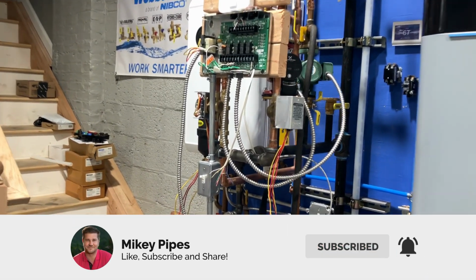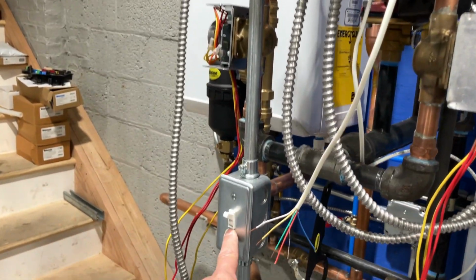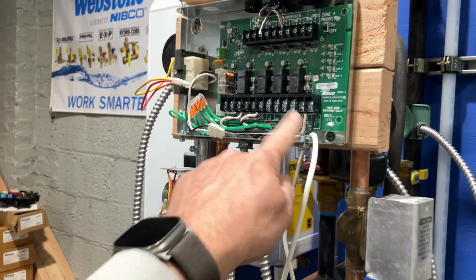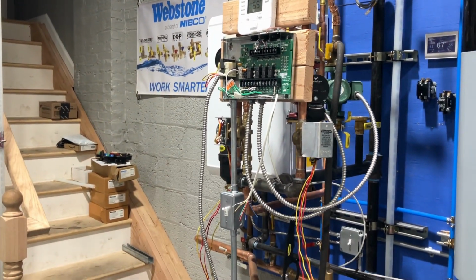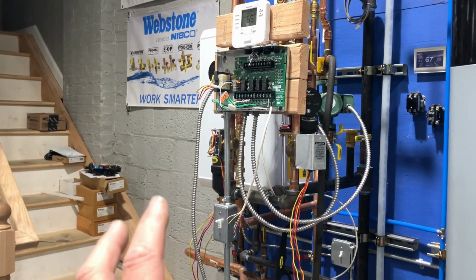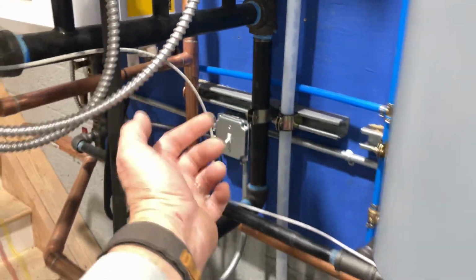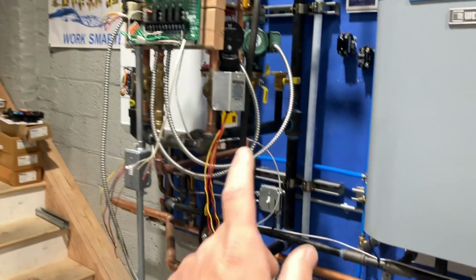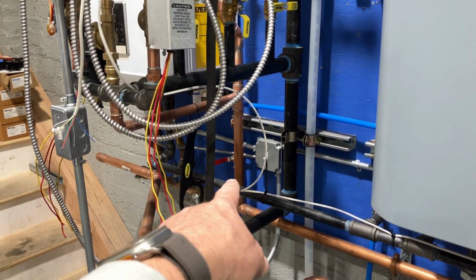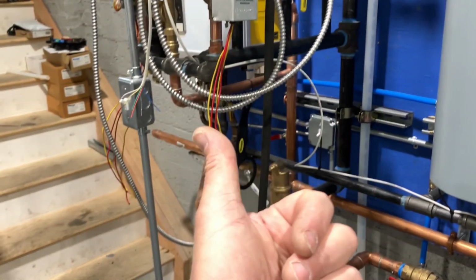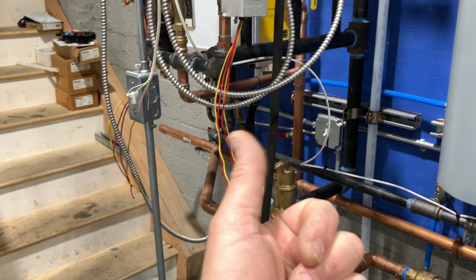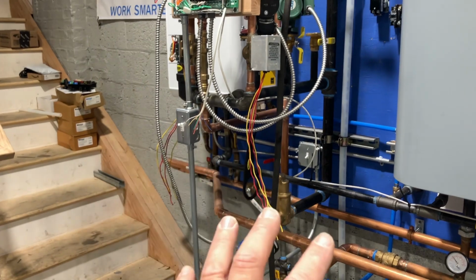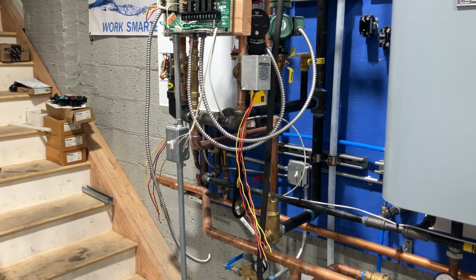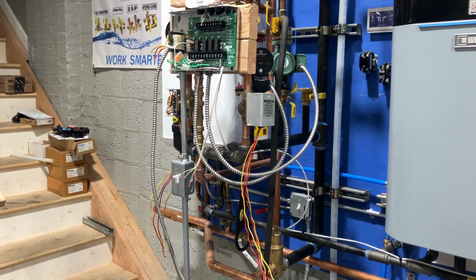Because now if, for example, the switch is on at the top of the stairs and you have no voltage here, you can go as far as your experience brings you, but never past the junction box, like that junction box, which brings in voltage to the mechanical equipment, whether it's the boiler, the furnace, the relay, what have you. That's where our liability stops, right? We can't troubleshoot past that. So if you check the circuit breaker panel, it doesn't appear to be tripped, everything appears to be on, and there's no voltage to the equipment, unless you have an electrical license behind you, your responsibility stops there. Now you need to refer the end user, the client, to a licensed electrician.